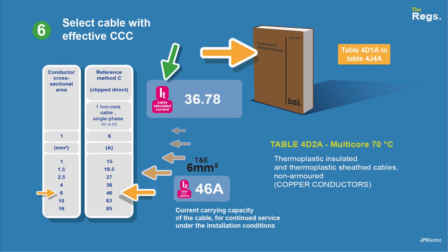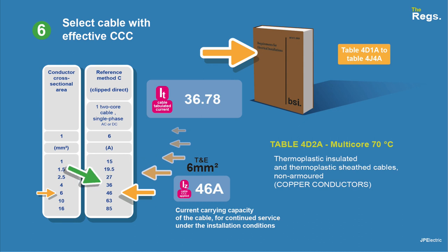With our IT of 36.78 amps, we need to find a cable that can carry that. There are many tables in BS 7671 depending on cable type and conductor type. We're going to use Table 4D2A — multicore 70 degrees C, thermoplastic insulated and thermoplastic sheathed cables. Looking through the table at reference method C, clipped direct, at 36.78 amps: 4mm² gives 36 amps — that's not sufficient. So 6mm² gives 46 amps, which is higher than 36.78. So we're going to use 6mm² cable. The current carrying capacity for continued service under installed conditions, that's your IZ, is 46 amps.